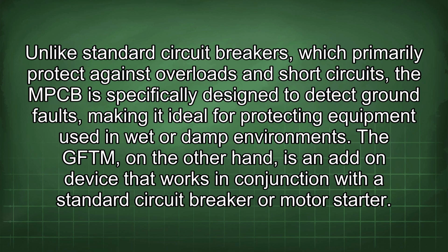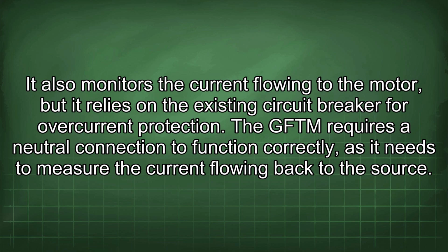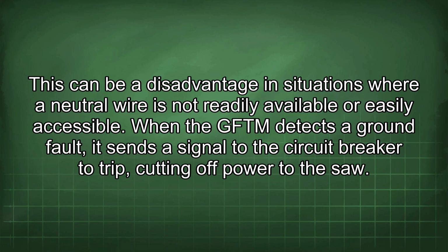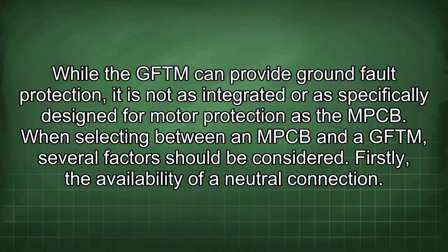Unlike standard circuit breakers, which primarily protect against overloads and short circuits, the MPCB is specifically designed to detect ground faults, making it ideal for protecting equipment used in wet or damp environments. The GFTM, on the other hand, is an add-on device that works in conjunction with a standard circuit breaker or motor starter. It also monitors the current flowing to the motor, but it relies on the existing circuit breaker for overcurrent protection. The GFTM requires a neutral connection to function correctly, as it needs to measure the current flowing back to the source. This can be a disadvantage in situations where a neutral wire is not readily available or easily accessible. When the GFTM detects a ground fault, it sends a signal to the circuit breaker to trip, cutting off power to the saw. While the GFTM can provide ground fault protection, it is not as integrated or as specifically designed for motor protection as the MPCB.